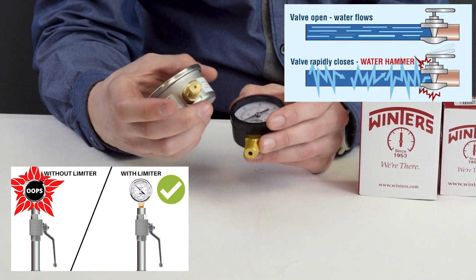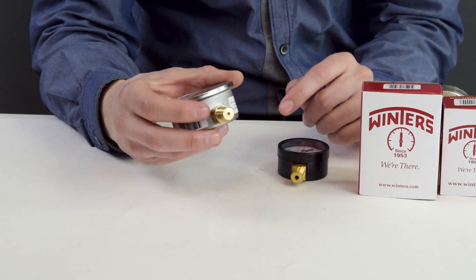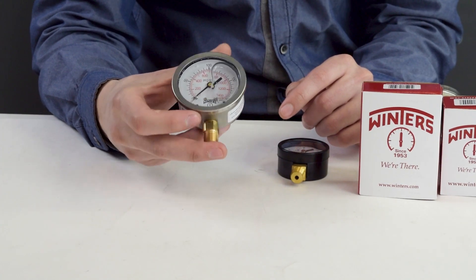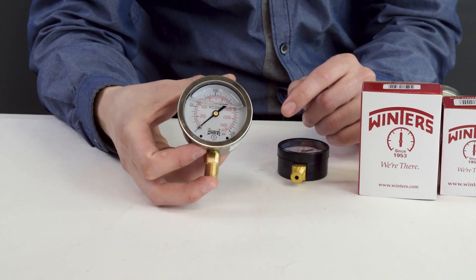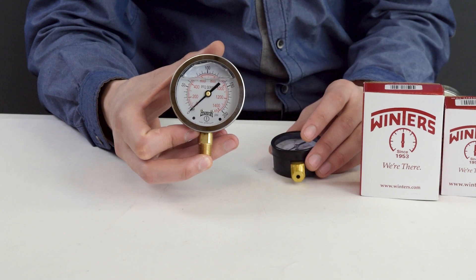The standard PFQ comes with leaded brass. However, if you have an application that has potable water, you're going to want a gauge that has lead-free brass to meet the Safe Drinking Water Act. When it has LF at the end of the part number, it stands for lead free — not liquid filled.